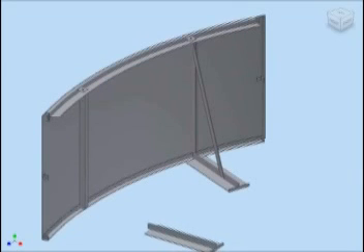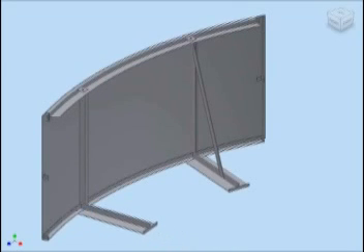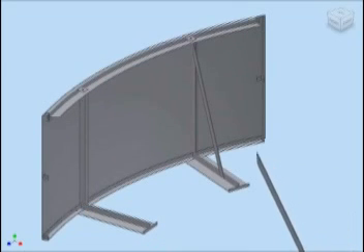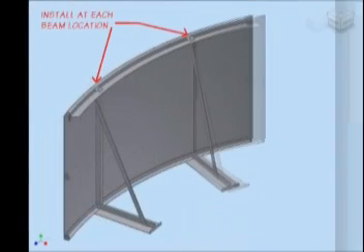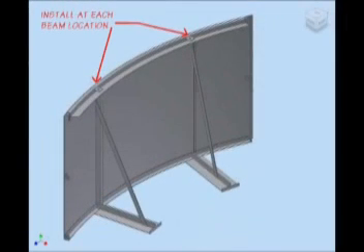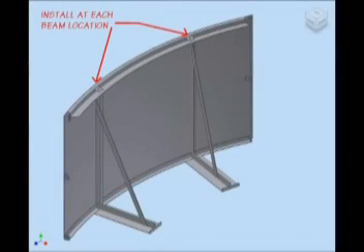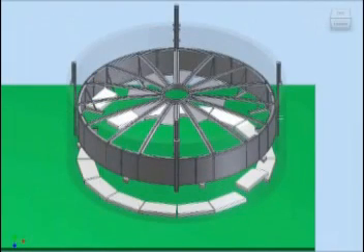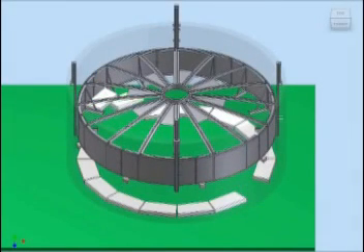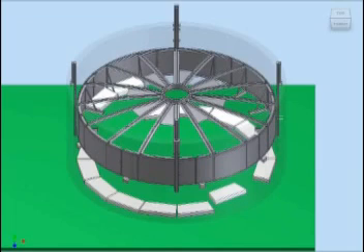Before ballast blocks are installed, the ballast supports and lower side sheets shall be painted with a final coat. While the cover is sitting on the corbels, lift the ballast blocks into place working from opposite sides of the tank to balance the framework.